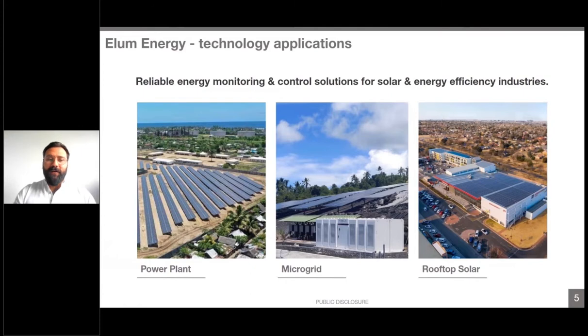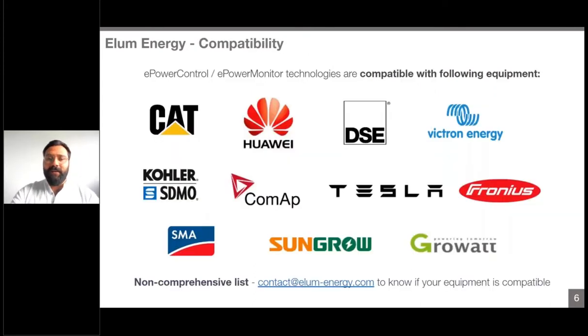So we are operating in several fields. I'll be focusing today on the C&I buildings, so commercial and industrial buildings. But I want to mention that we are operational in utility scale projects, power plants, and microgrid systems. Our main added value in Elum is our compatibility with a lot of different brands. As you can see here, there are the main players like Huawei, Tesla, Fronius, Sungrow, Caterpillar. These brands range from genset controllers, PV inverters, and PCS of the batteries. This gives flexibility to our client to choose their own brands. The only requirement that we ask for is to have the Modbus protocol in order to integrate any brand.